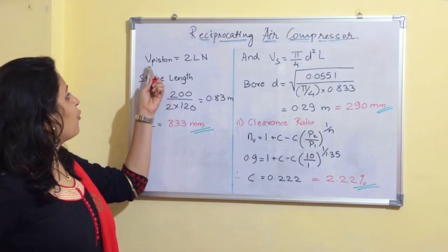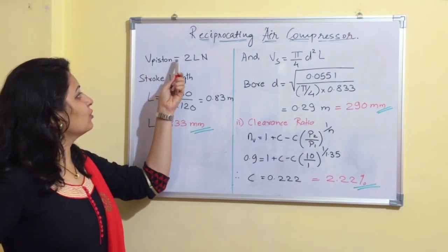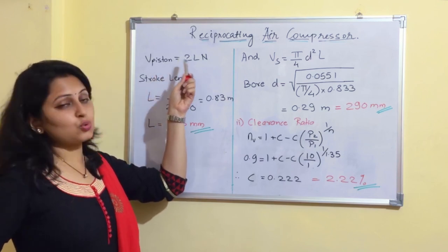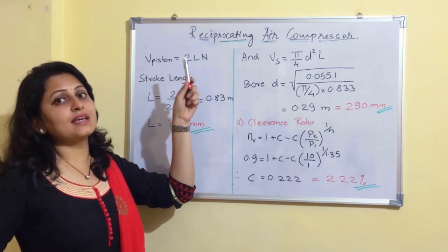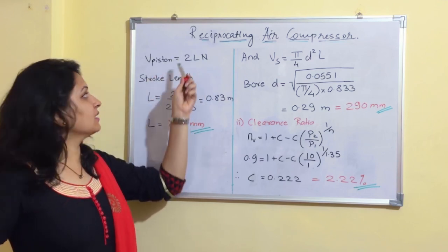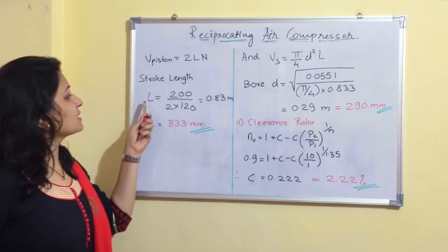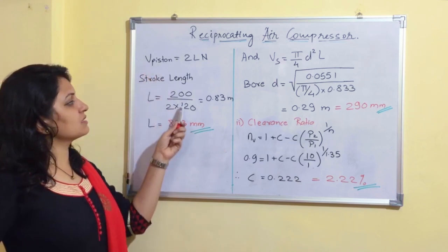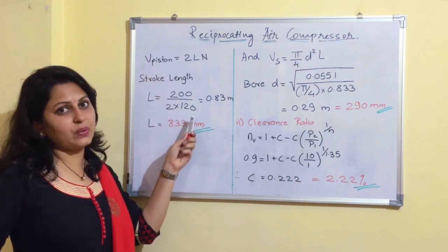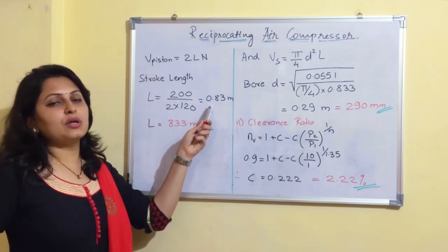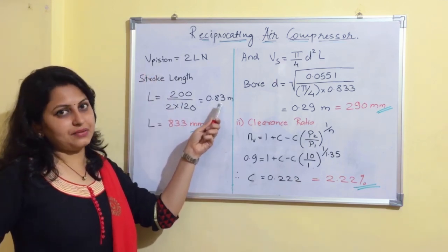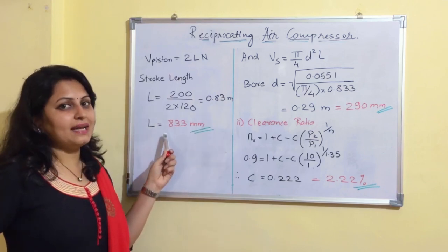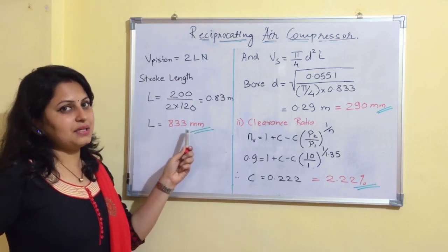The formula for piston speed is 2LN for double acting (and LN for single acting). Substituting the piston speed of 200 m/min and N = 120 rpm, we get stroke length L = 0.83 m, which equals 833 mm.